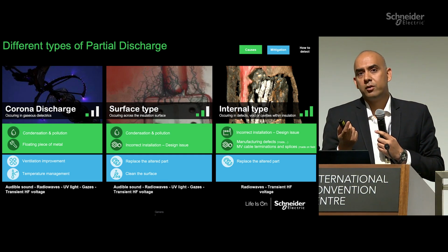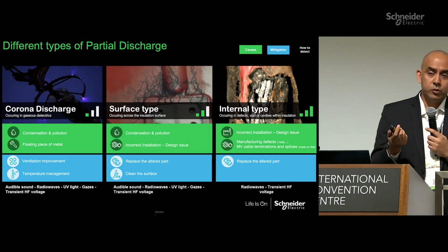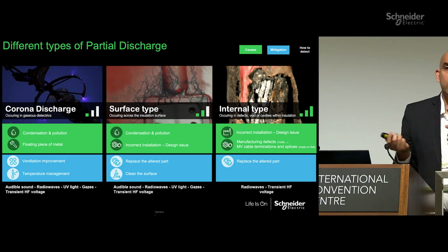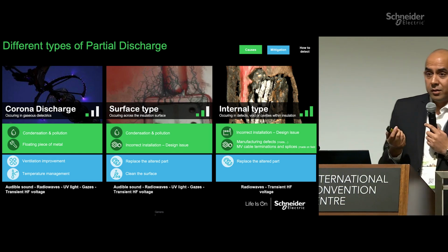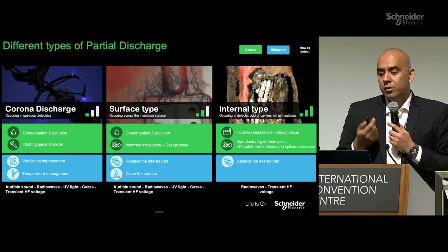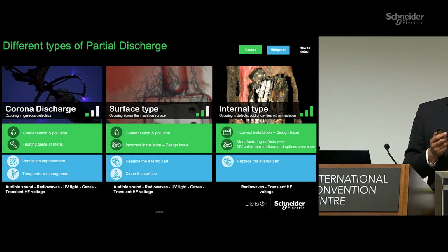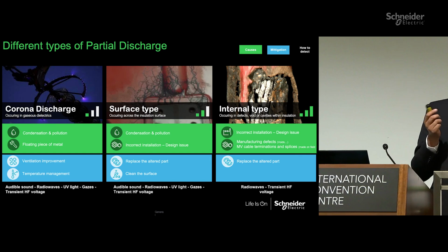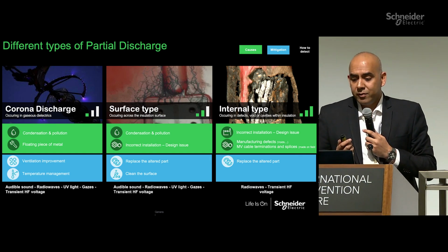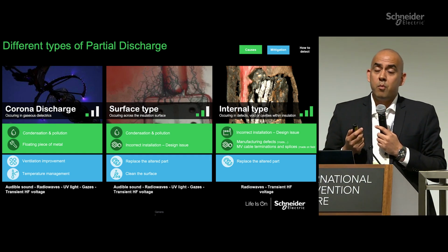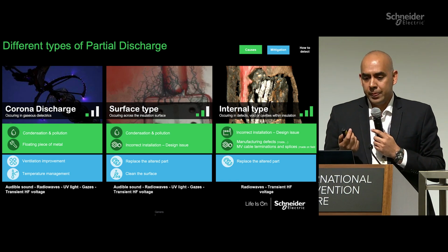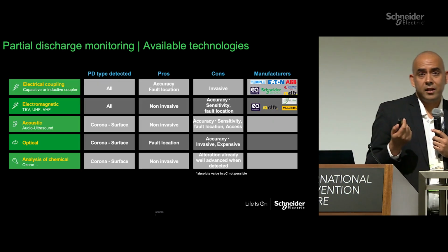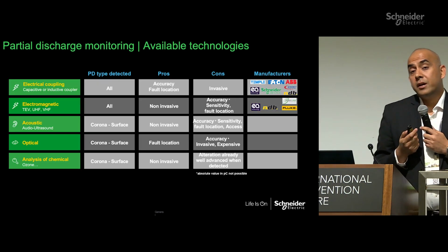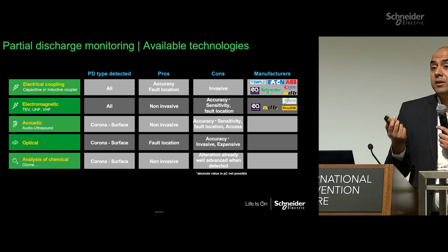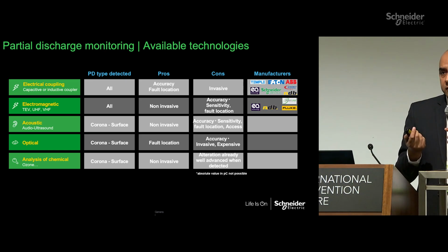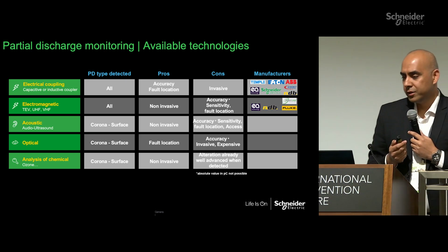And it's very, very dangerous because you cannot hear it, you cannot see it, so you do not know whether it's happening or not. And the only way to measure it is through radio waves or through transient voltage measurement, which is often very difficult. So you need specific sensors to measure it. And this is where the whole monitoring technology, etc., are coming in. Now, how do we measure partial discharge? Because of course, you've understood the issues which are happening, what the different types of discharges are, but how do we mitigate it? Through measurement and of course, monitoring technologies.